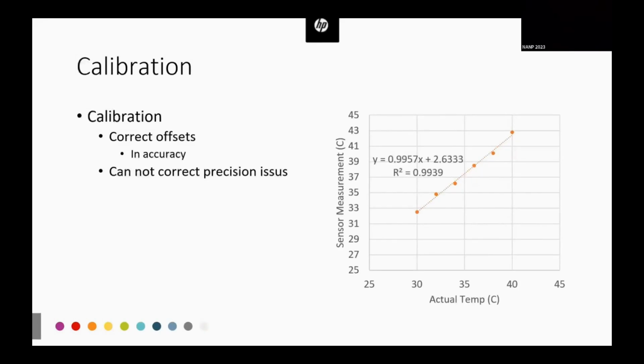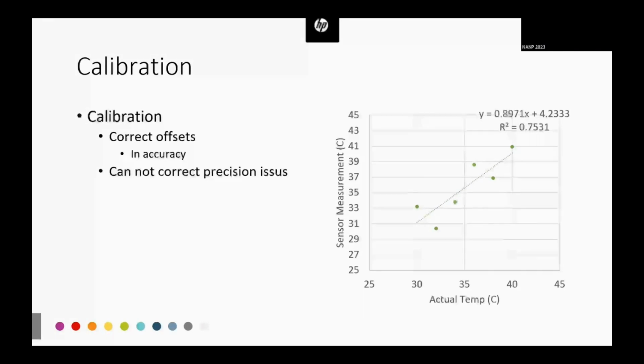Here we have a sensor that is very precise but has an offset of 2.5 degrees, so you can easily calibrate it to pull that back down and make it accurate and precise. In this case, we might have an accurate sensor, but not a very precise one, or neither accurate nor precise. We can do a calibration to help improve accuracy, but with a lot of scattering around that point, it's not going to improve it completely.